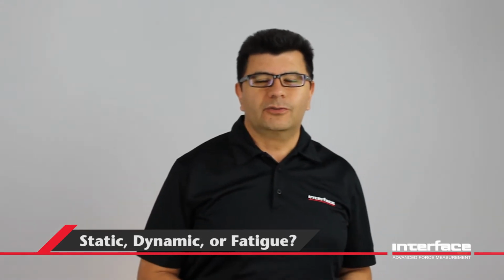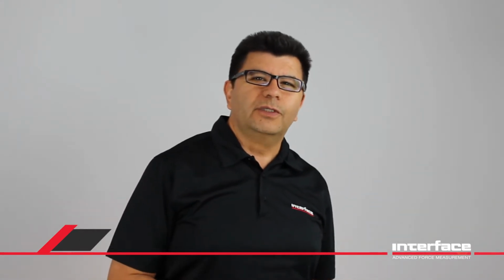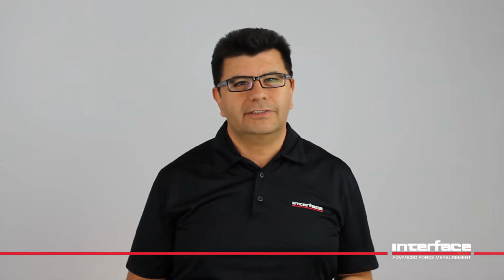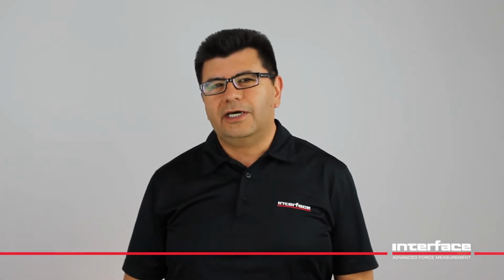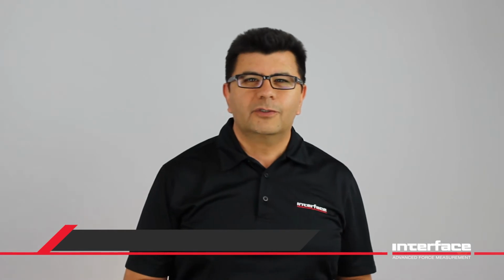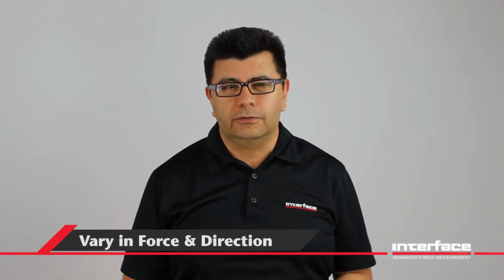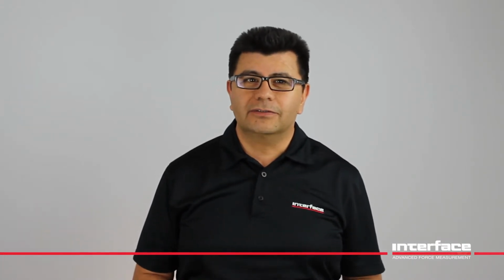Will it be a static, dynamic, or fatigue measurement? A static measurement is a force applied to the load cells in only one direction, tension or compression, from 0 to 100, constant for an extended period of time. A dynamic measurement has loads that vary in both force and direction. A fatigue measurement is one with multiple cycles from 100% compression to 100% tension load.